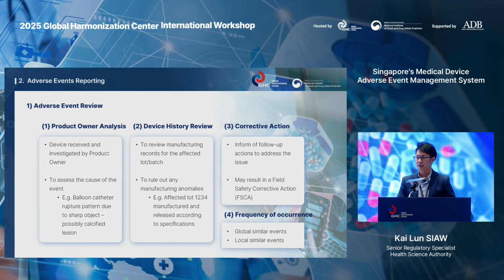So during adverse event review, what we look out for is what resulted in the event, or what we call causality assessment. We look for a few things during our review for each adverse event. One of the important ones, I would think, is product owner analysis. The device in an ideal situation will be returned to the product owner for inspection and analysis. Once received, they will have to assess what caused the event to occur. For example, if a balloon catheter ruptured, the components of the balloon catheter will be returned to the product owner. From there, they will deduce, oh, this rupture, the line is very clean, so it's probably due to a sharp object poking it, possibly a calcified lesion. From there, we can determine the root cause of it.